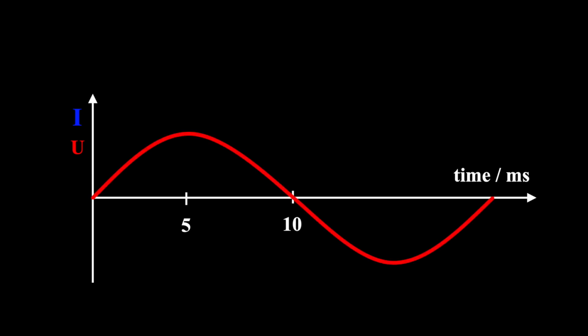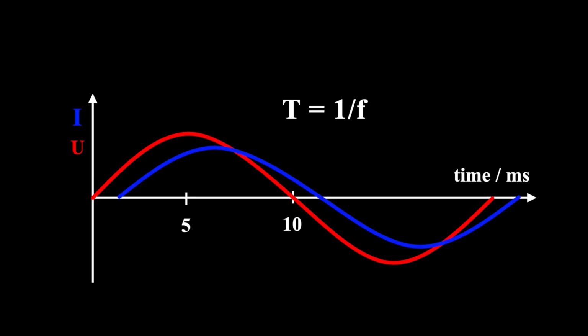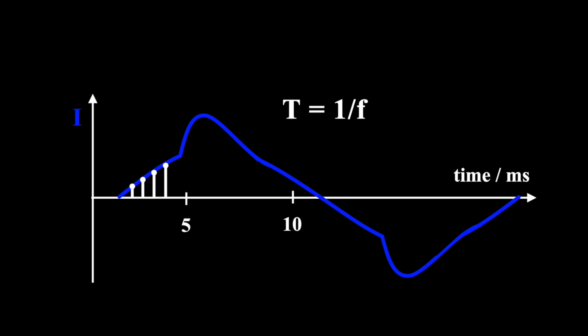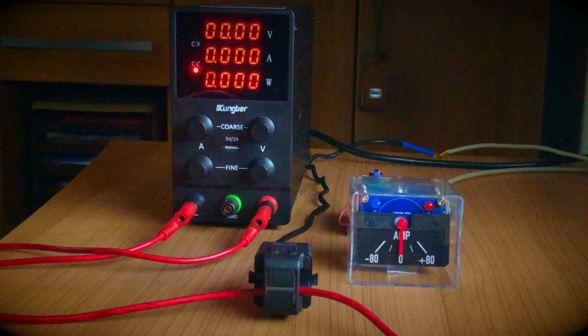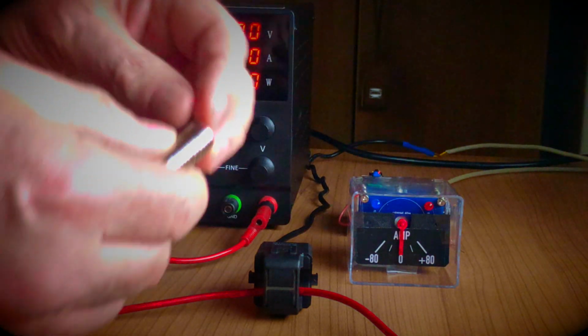Now we're going to a milliseconds timescale instead of microseconds. This is the voltage in a 50 Hz power grid. One period is 20 milliseconds. A consumer's current could be sampled more than 6,000 times per period with that sensor, sufficient for analyzing phase shift and spikes. Just as a side note, we could connect an oscilloscope directly to the sensor to analyze the current flow. A Hall sensor is measuring indirectly via the current's magnetic field, so it seems obvious a magnetic field can interfere.